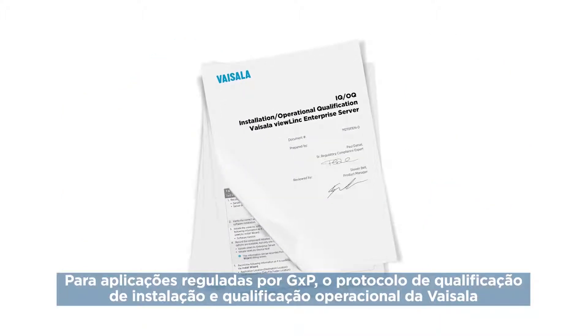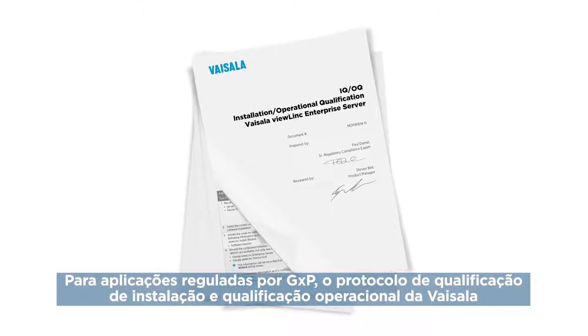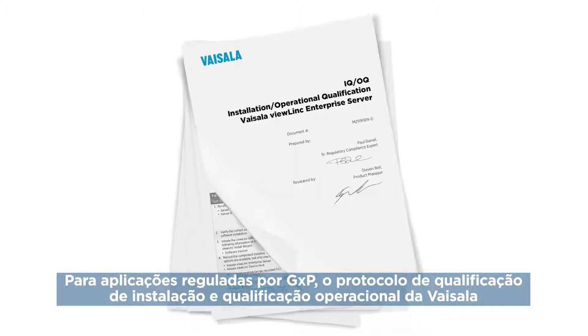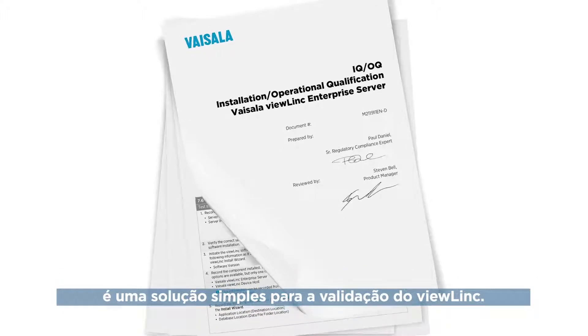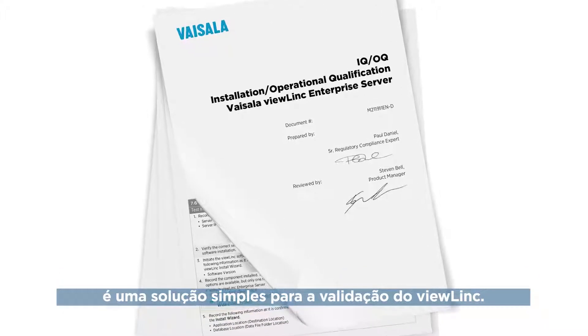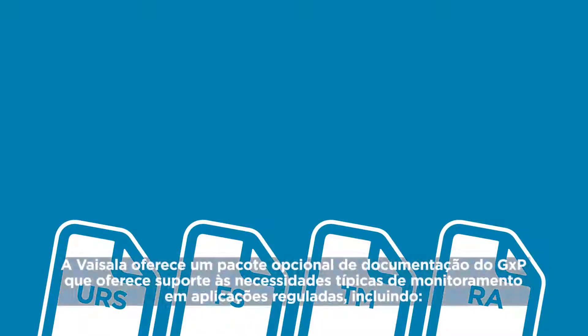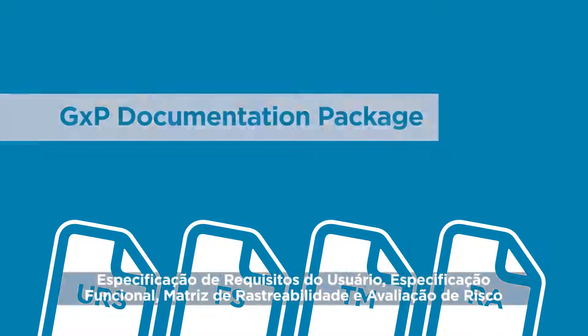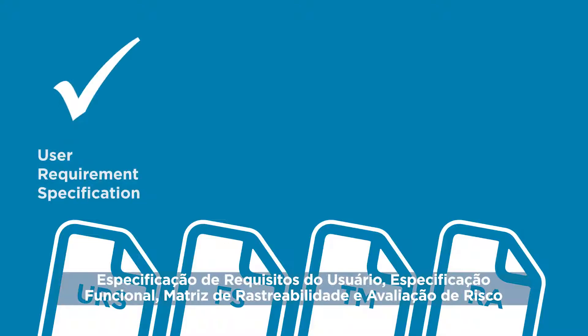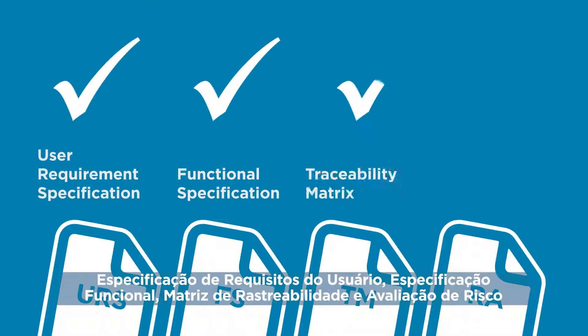For GXP-regulated applications, Vaisala's installation qualification and operational qualification protocol is a simple solution for validating viewLinc. Vaisala offers an optional GXP documentation package that supports the typical needs of monitoring in regulated applications, including user requirements specification, functional specification, traceability matrix and risk assessment.